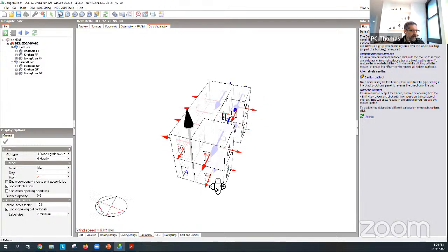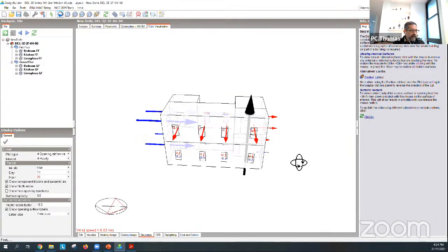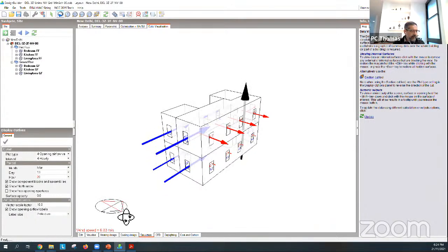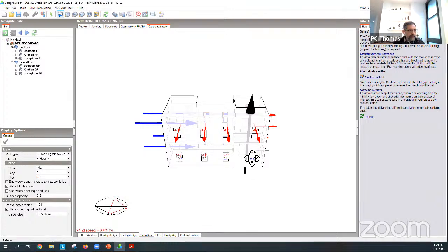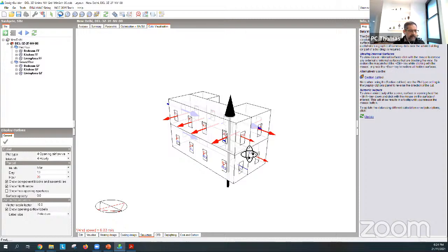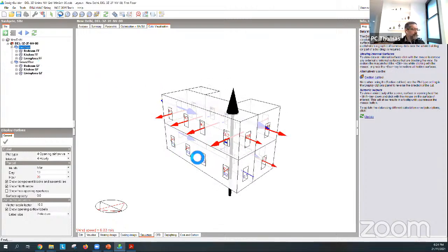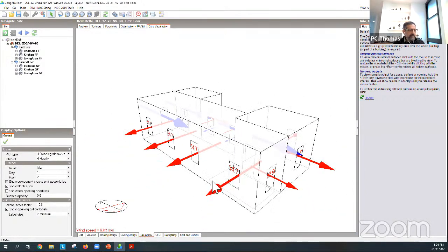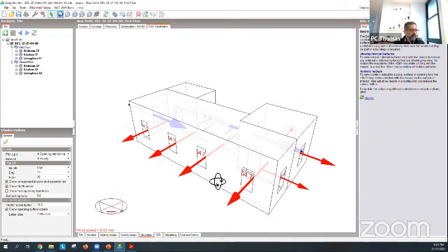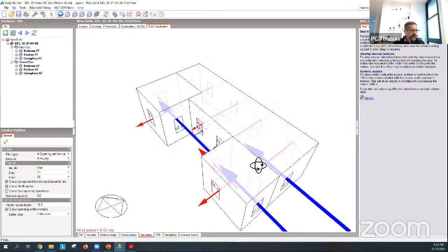Okay, so this is a very windy hour, and the wind just happens to be right at the correct direction. The wind direction is pushing air through there, and you can see a lot of the wind is coming up from the bottom to the top floor through that staircase hole that we cut. And it's actually telling us, so if you went to the first floor, then you can work out how much air is actually going out and coming in during that hour. So you can spin the model around and you know how it's working.